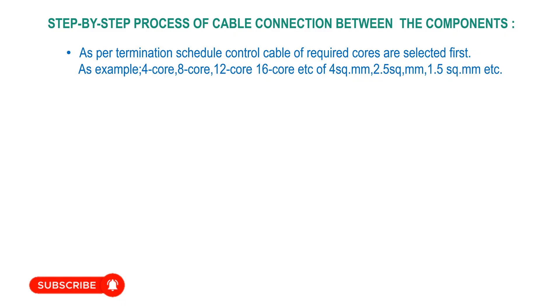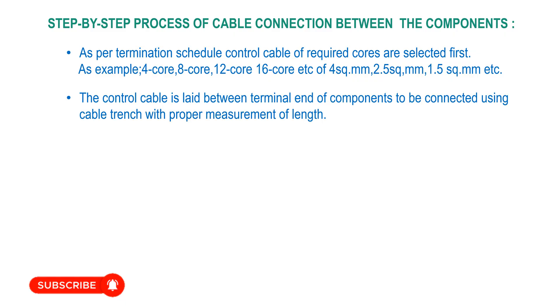As per the termination or cable schedule, control cables of the required number of cores are selected first — for example, 4-core, 8-core, 12-core, or 16-core — of 4mm², 2.5mm², or 1.5mm² cross-section. Then the control cable is laid between the termination ends of the components to be connected, using the cable trench with proper measurement.